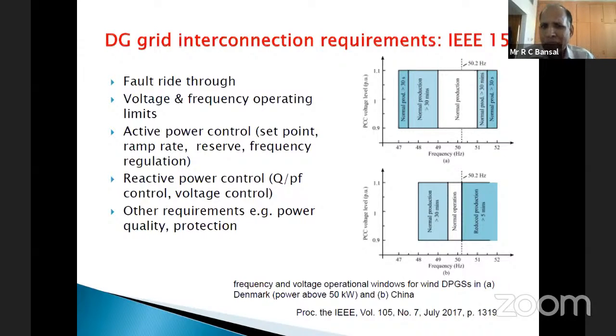Again, as I mentioned, one of the key requirements is to maintain active power control, the system frequency, reactive power control, and the voltage. These two, frequency and voltage, are extremely important control parameters which we have to maintain. Just to give you an example, you can see here two cases. One is for Denmark, and the one below is for China, for frequency and voltage control. For the Denmark case, if the system is under normal operation, the frequency can vary between 49 and 51 Hz.